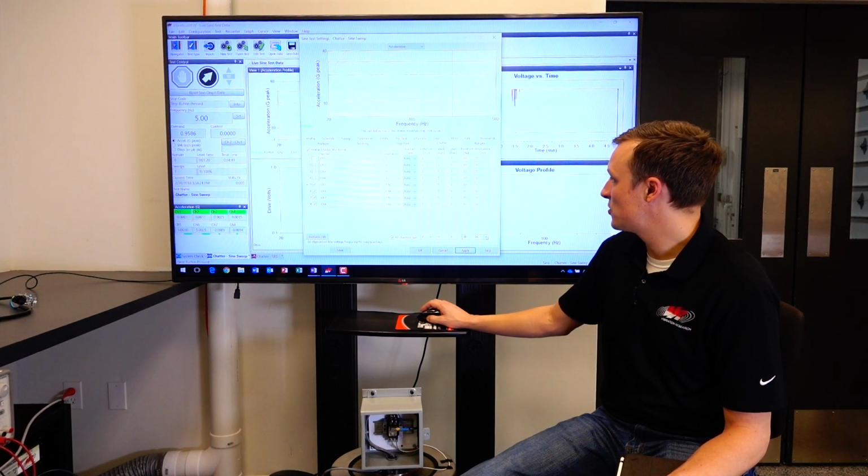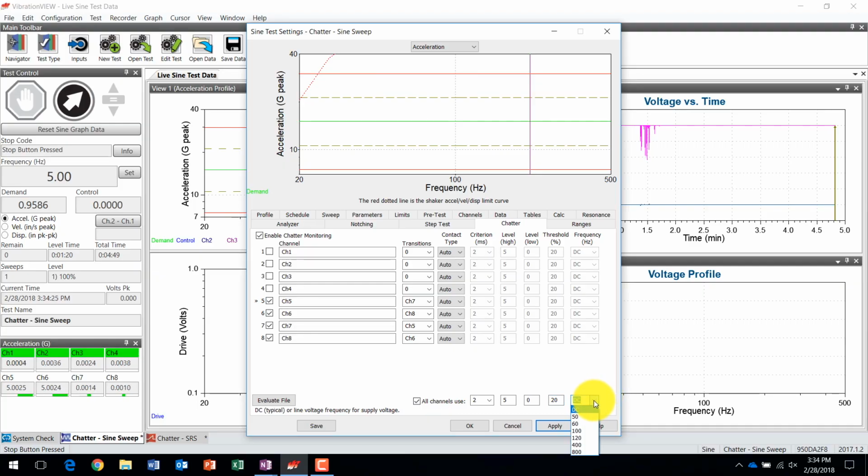Finally is the frequency, or DC. That means if I'm in the United States, I would expect the frequency of an AC signal to be at 60 hertz. If I'm in Europe, it would be 50 hertz. If you're using a variable frequency drive, it could be a variety of things. This is a custom entered value. We do have some predefined frequencies in there, but you do not have to use them. In today's demonstration, I'm using a DC power supply, so I'm going to select DC.